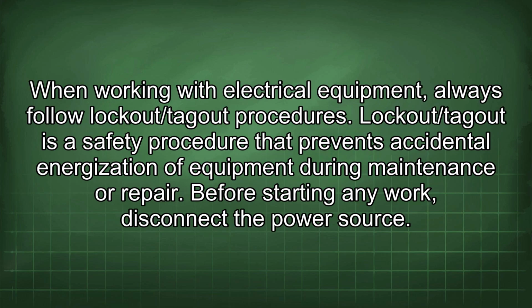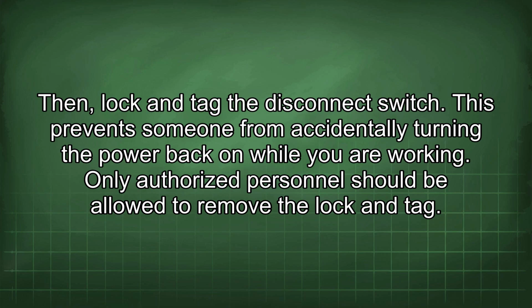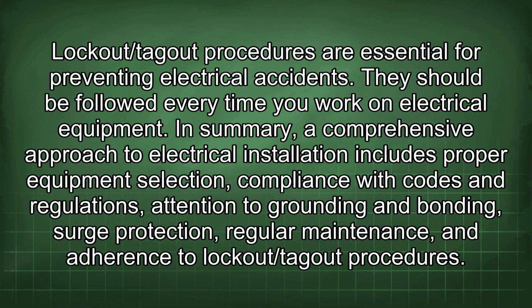When working with electrical equipment, always follow lockout/tagout procedures. Lockout/tagout is a safety procedure that prevents accidental energization of equipment during maintenance or repair. Before starting any work, disconnect the power source, then lock and tag the disconnect switch. This prevents someone from accidentally turning the power back on while you are working. Only authorized personnel should be allowed to remove the lock and tag. Lockout/tagout procedures are essential for preventing electrical accidents. They should be followed every time you work on electrical equipment.